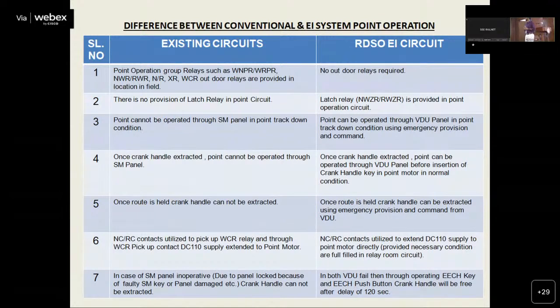Once a route is held, the crank handle cannot be extracted. In the conventional system, we first had to release that particular route before extracting the crank handle. But here, an emergency option is available from the panel itself. Using ID and password, we can release the crank handle, and after 120 seconds, that particular crank becomes available. With that crank, the point can be operated even if the route is held.